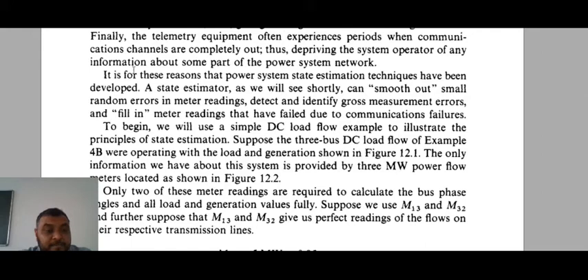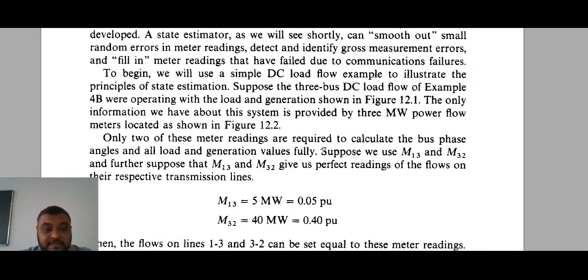It is for these reasons that power system state estimation techniques have been developed. A state estimator can smooth out small random errors in meter readings, detect and identify gross measurement errors, and fill in meter readings that have failed due to communication failures that we discussed earlier.